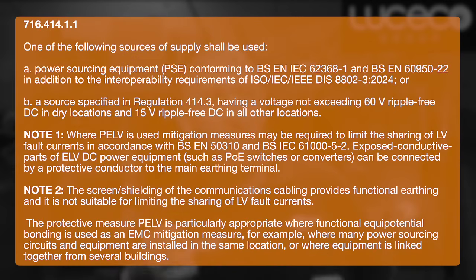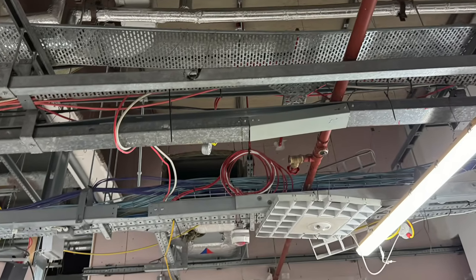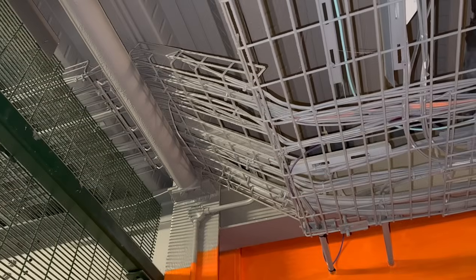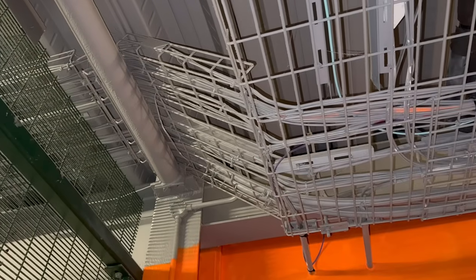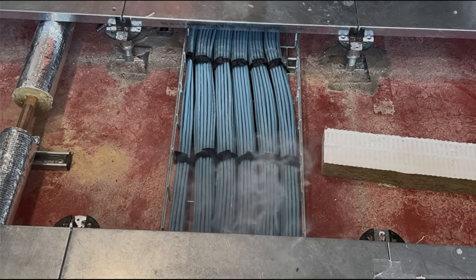Regulation 716.414.1.1 sets out the permitted sources of supply for these systems. It must come either from power sourcing equipment that meets the relevant product standards or from a source that meets the requirements for SELV or PELV, with a maximum of 60 volts ripple-free DC in dry locations and 15 volts ripple-free DC in all other locations. So although this looks like a simple data system, the safety of the supply is being tightly controlled at the source, so the voltage itself is not the main concern. The issue is current and heat.